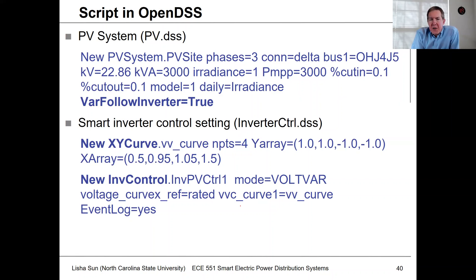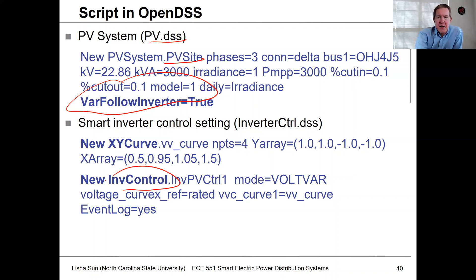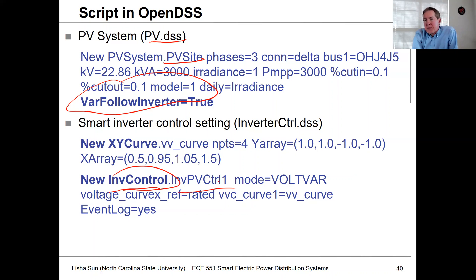To do this in OpenDSS, we need to augment the PV site definition to include smart inverter functionality. In PV.DSS, we add the flag 'var_follow_inverter = true'. Then we need to define a controller — the object type is 'InverterController', and we define an instance called 'InverterPVControl1'. The mode will be volt-var mode.